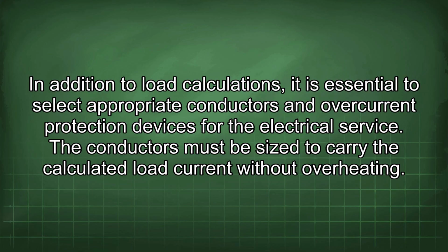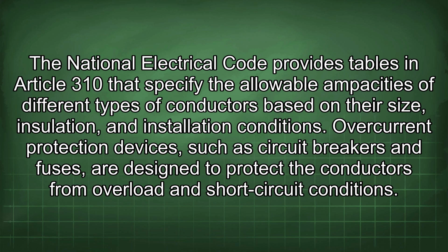The conductors must be sized to carry the calculated load current without overheating. The National Electrical Code provides tables in Article 310 that specify the allowable ampacities of different types of conductors based on their size, insulation, and installation conditions. Overcurrent protection devices, such as circuit breakers and fuses, are designed to protect the conductors from overload and short-circuit conditions.